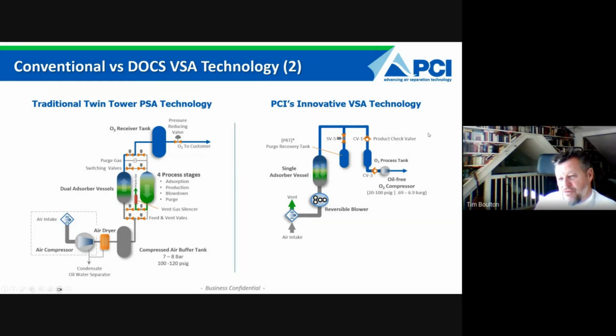The oxygen produced then goes through here into a process tank, and there is also a purge recovery tank. I'll get back to that in a minute. And then there is a second stage. So this is just one stage. As I said, the pressure going to the hospital pipeline is generated at the point of intake. Here it's a low pressure intake, less than 1 bar. And then the produced oxygen is pressured up to the required pressure by a second stage, an oil-free oxygen compressor. So that is the comparison of the two.